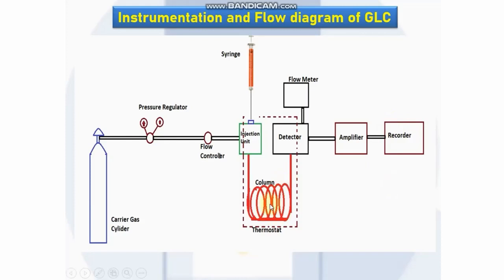The column is maintained at a constant temperature higher than the boiling point of the least volatile component in the sample mixture, with the help of a thermostat. The sample injection port and the detector unit are usually maintained at still higher temperatures to promote rapid vaporization of the injected sample and to prevent condensation in the detector. As soon as each component emerges from the column, the detector response is sent to a recorder.